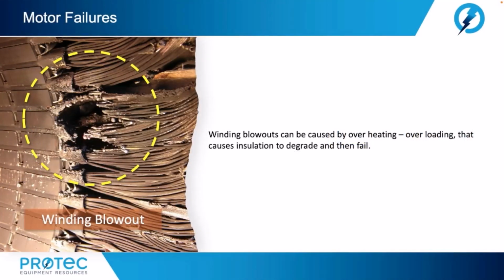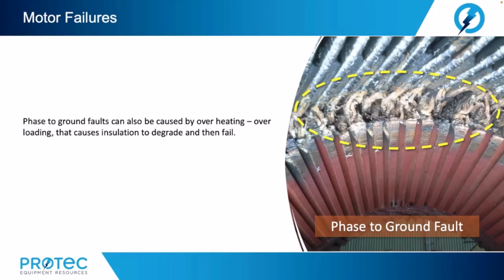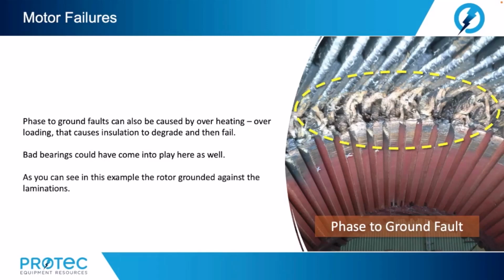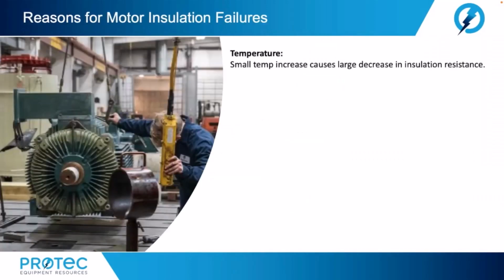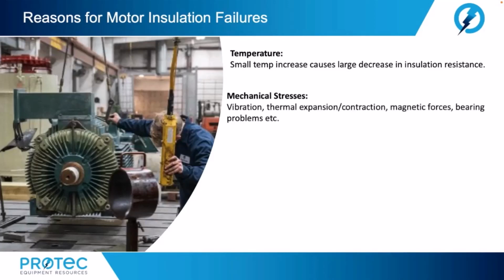First, let's look at winding blowout. Winding blowouts can be caused by overheating, overloading, that causes insulation to degrade and then fail. Also, phase to ground fault. Phase to ground faults can also be caused by overheating, overloading, that causes insulation to degrade and then fail. Bad bearings could have come into play here as well. As you can see in this example, the rotor grounded against the laminations. Now, other reasons might be temperature. Small temperature increase causes large decreases in insulation resistance. Or the failure could have been mechanical stresses, vibration, thermal expansion and contraction, magnetic forces, bearing problems, etc.